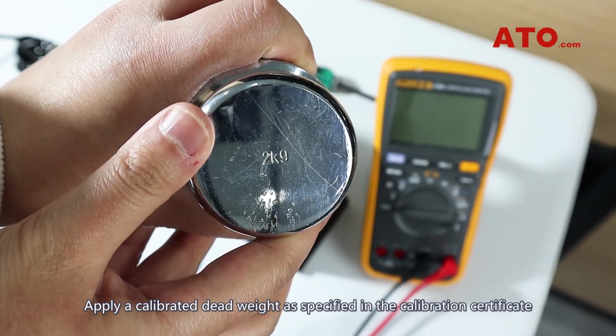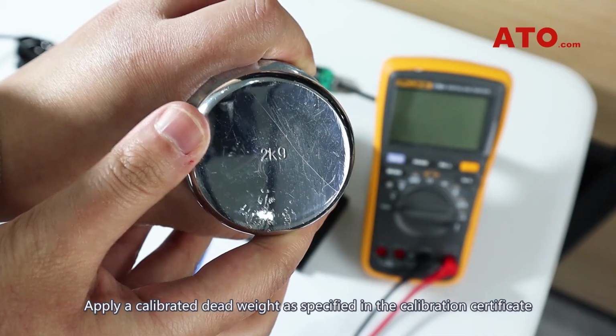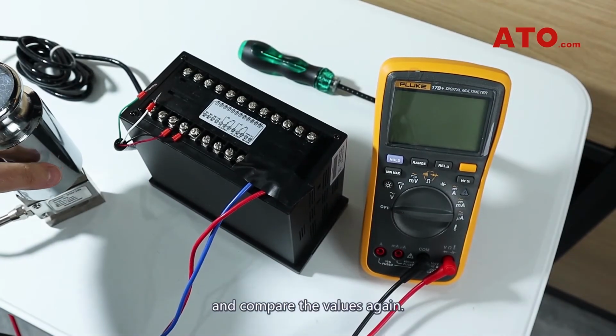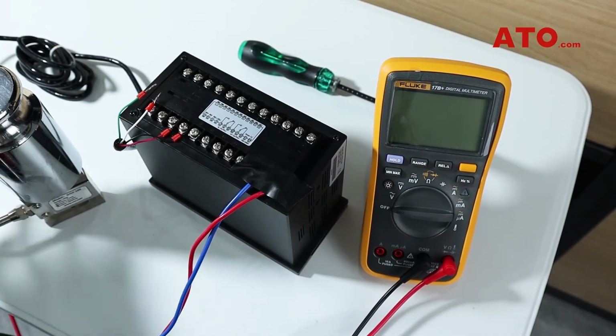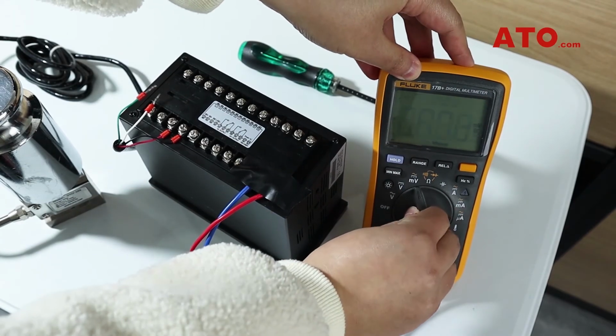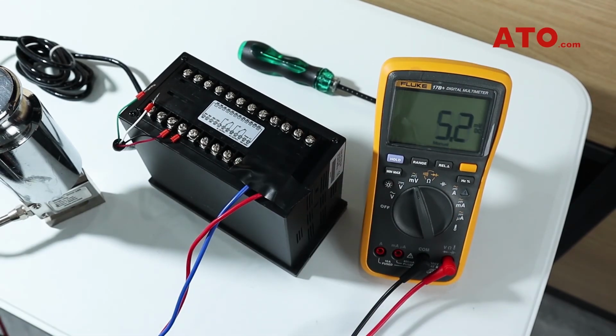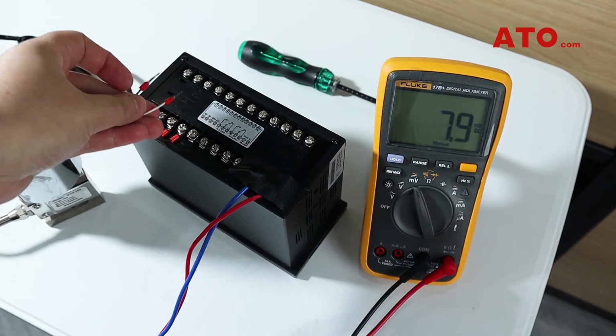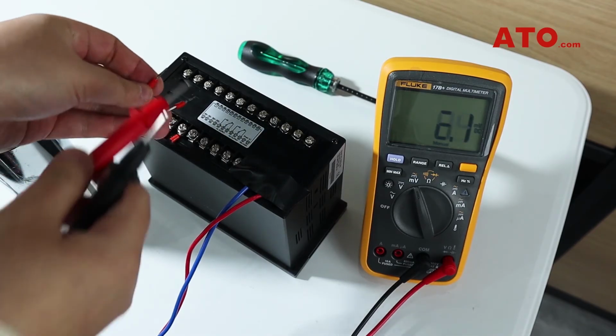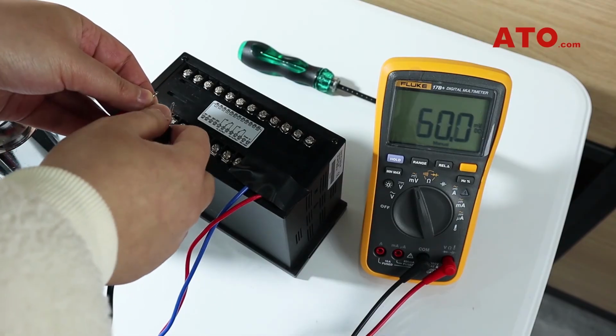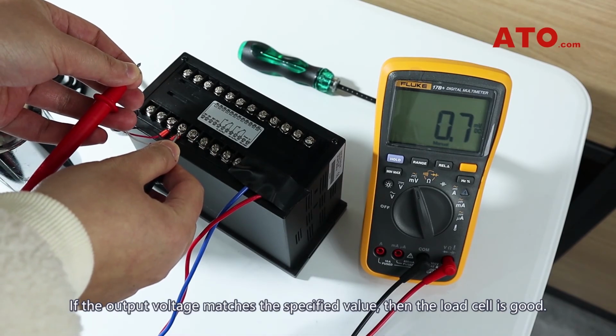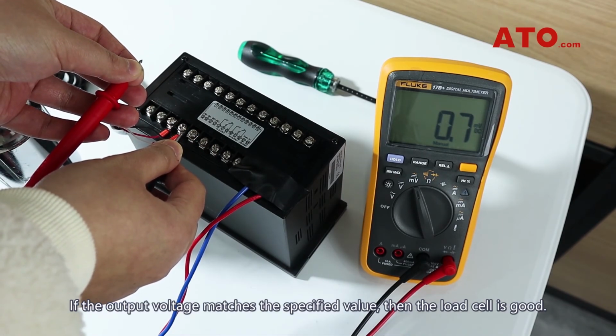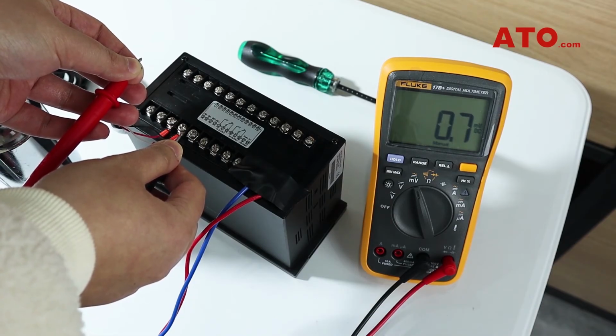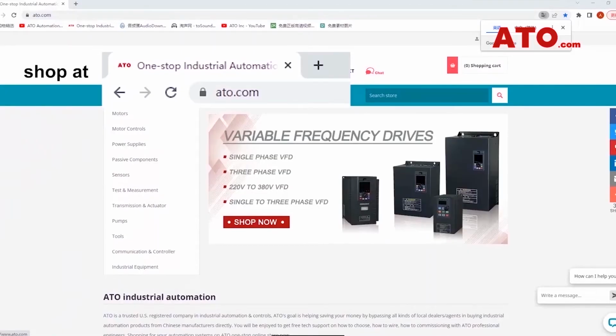Apply a calibrated dead weight as specified in the calibration certificate and compare the values again. If the output voltage matches the specified value, then the load cell is good. That wraps it up for the video.